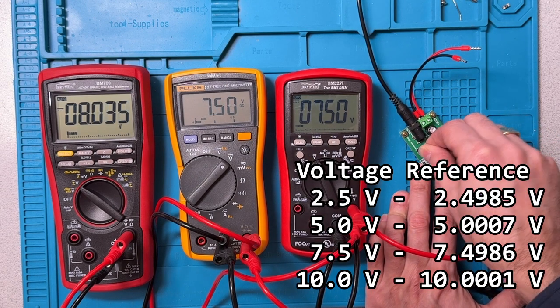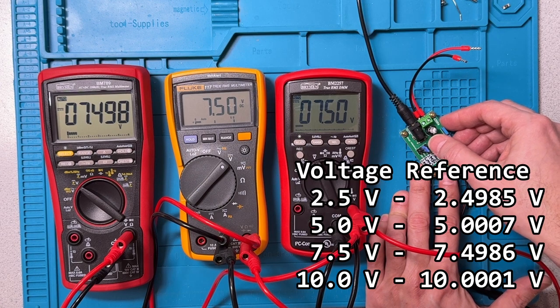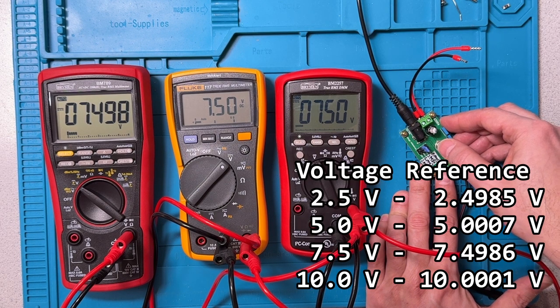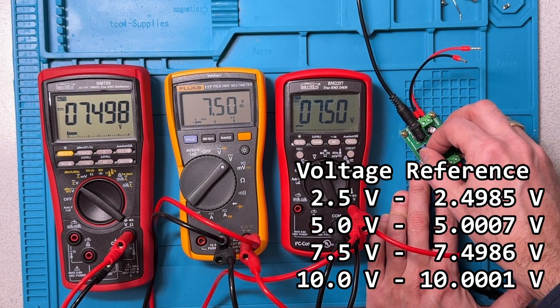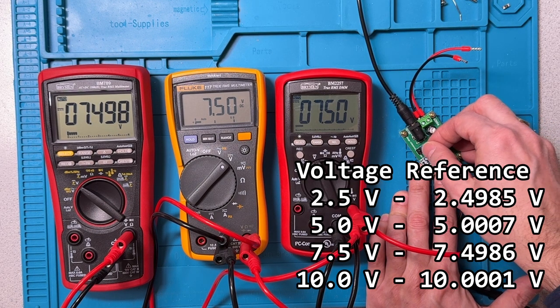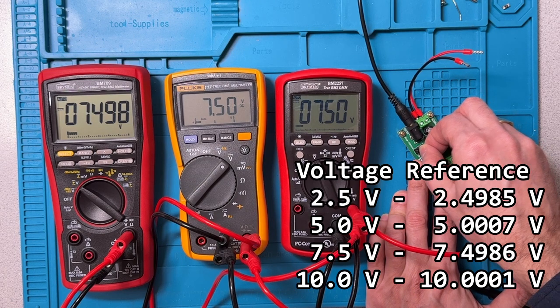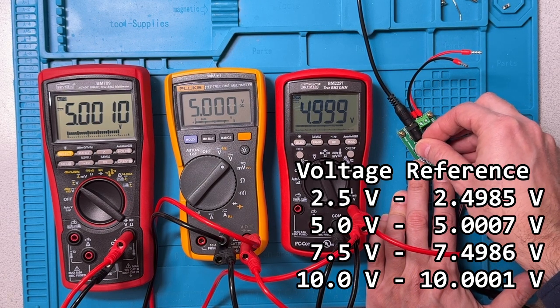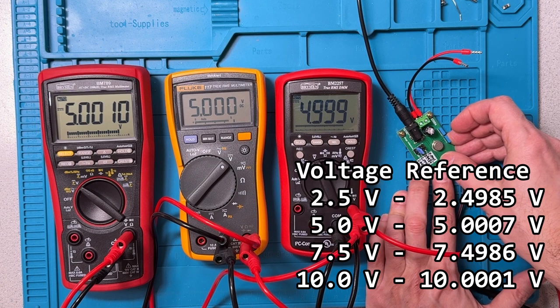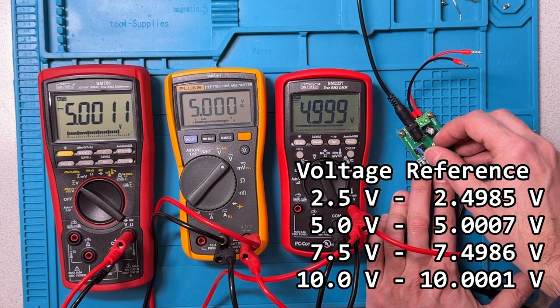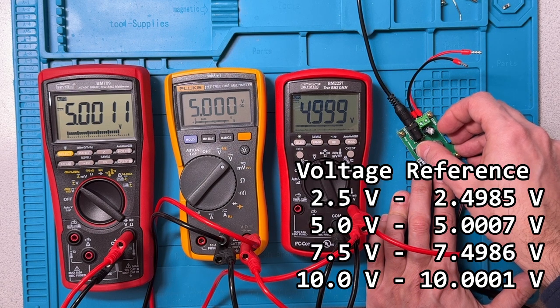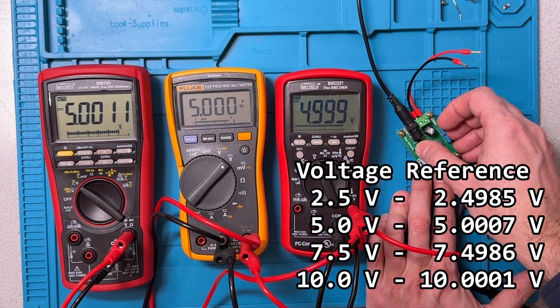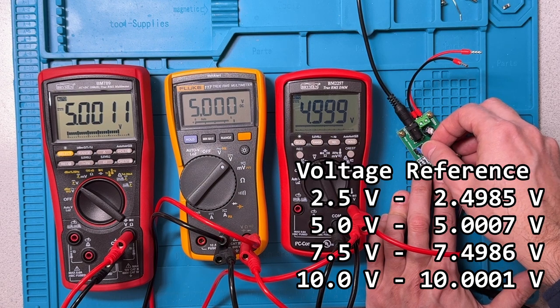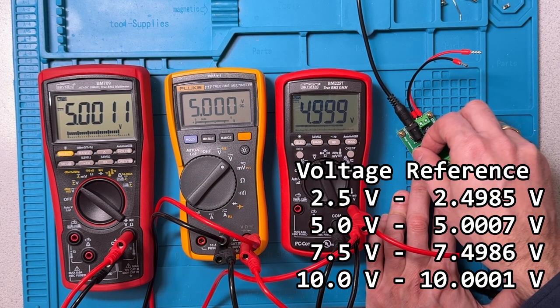Now, at 7.5 volts, we see that the 789 is closer. The 2257 and the 117 are both reading 7.5 volts dead on. At 5 volts, we should be a little bit above 5. The 2257 is a little bit below 5. And the Fluke is 5 dead on. The 789 is just a bit above 5, closer to where it should be.